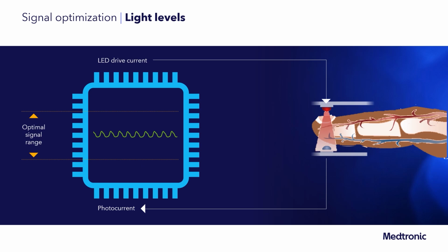In Nellcor, there is an algorithm that automatically adjusts the amount of light, or the amount of current that we send to the LED, as well as how much amplification we want to apply to that detector signal. And every time you put a Nellcor sensor on, it runs through that optimization algorithm to ensure that you're getting the best signal possible.